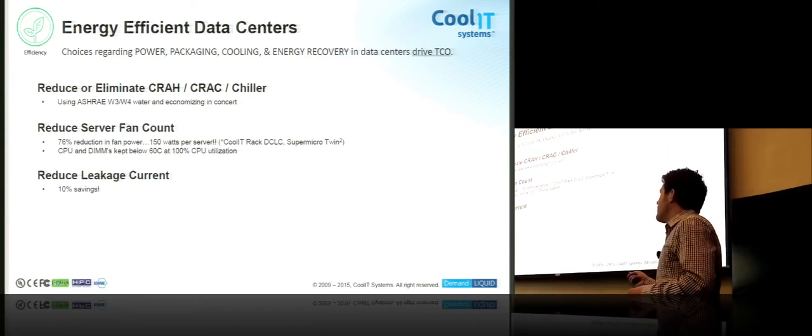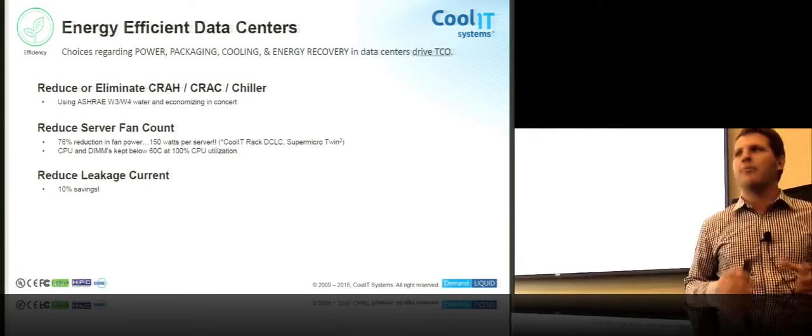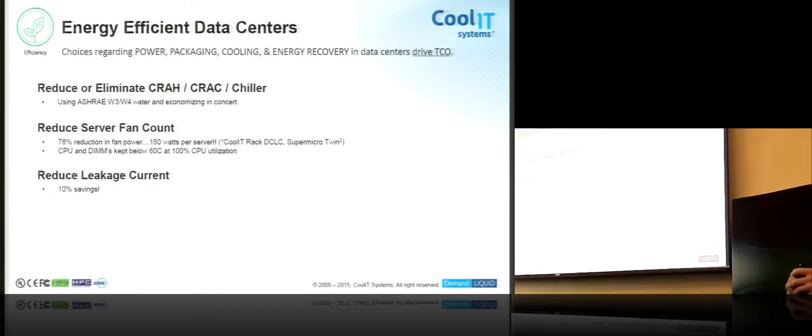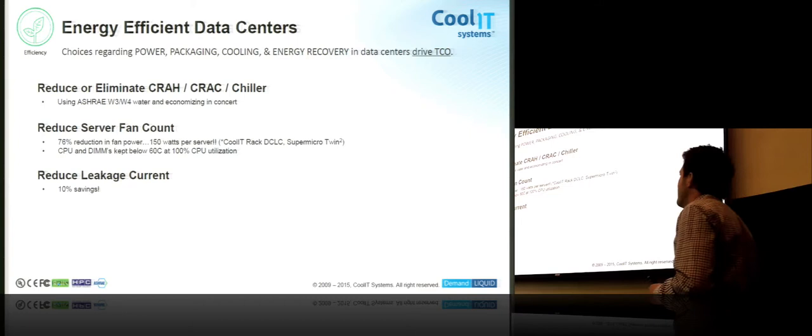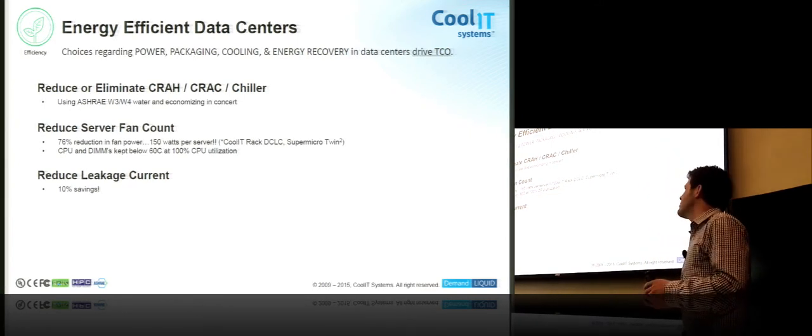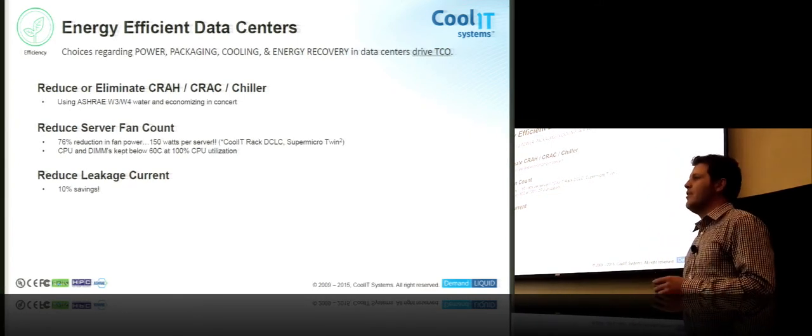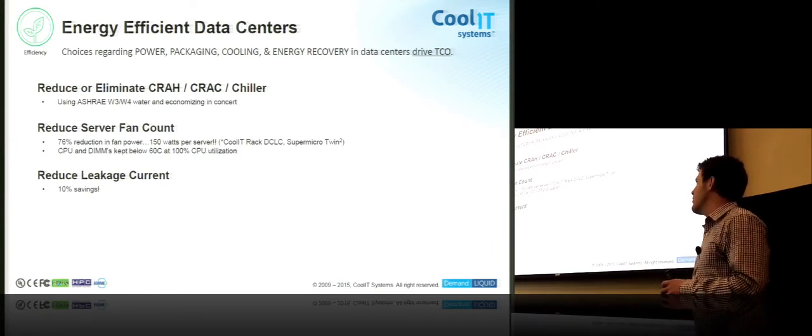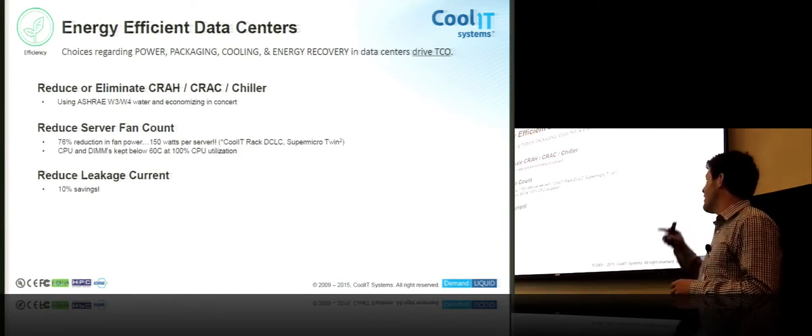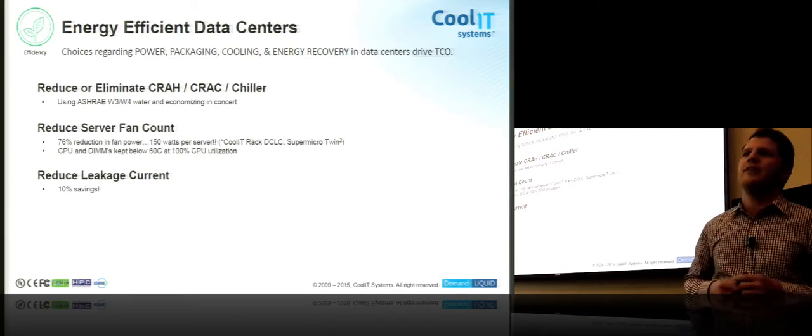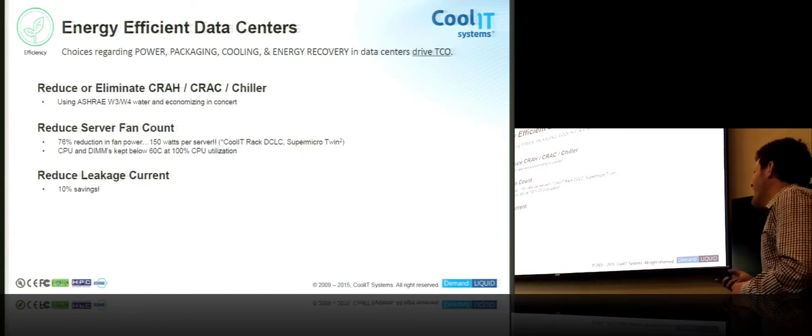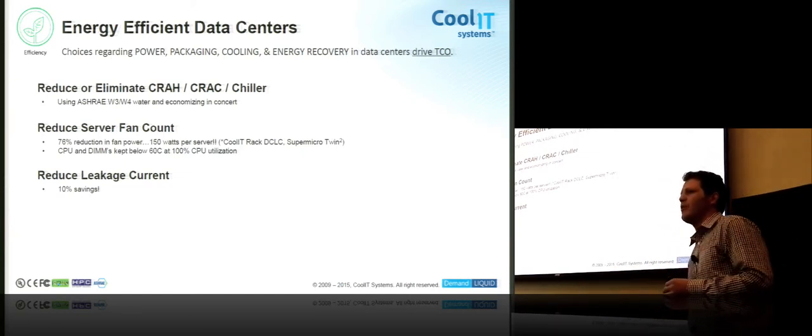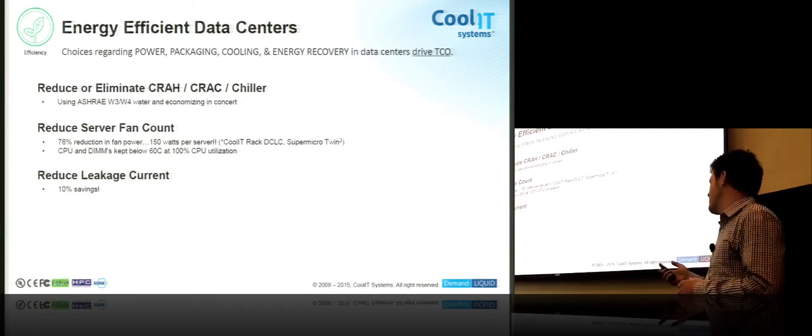In the server level, we also talk about efficiency. We can reduce the fan power, the total fan power consumption inside the server. We recently did a with Supermicro on their twin squared unit server. And we saw that we had a 76% reduction in fan power. So a total of 150 watts saved at each server. And that kept, that was at 100% CPU utilization. It kept the DIMMs and the CPU below 60C.